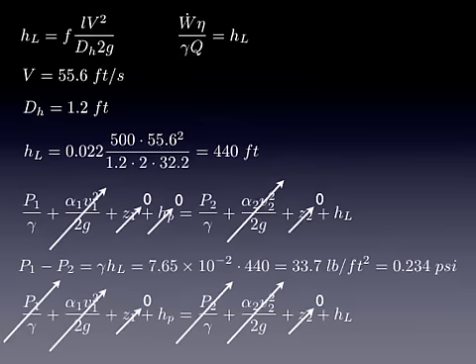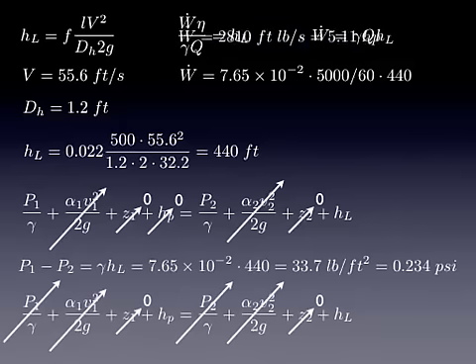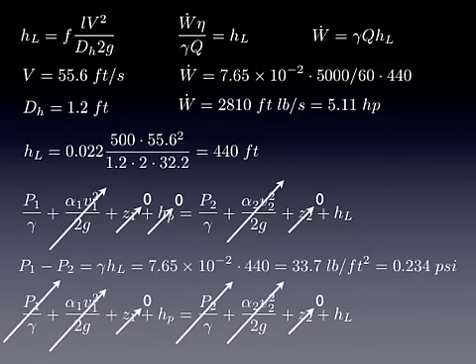We know what the head loss is already. It's 440 feet, so we don't have to resolve for that. We put in our pump equation and solve for the power. Note that I'm assuming an efficiency of 1. The question didn't give us any information on efficiency, so I just set that equal to 1. And we can solve for the power, and that's 5.11 horsepower.